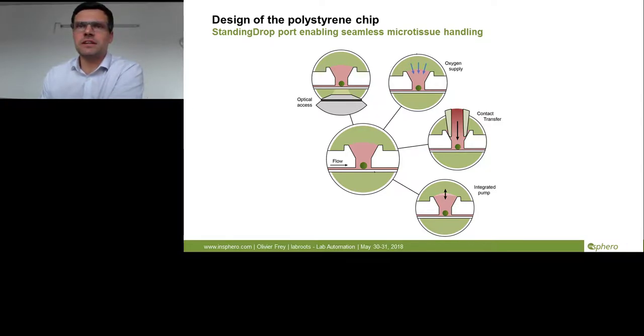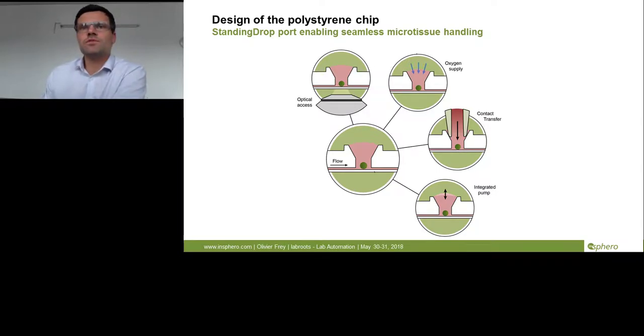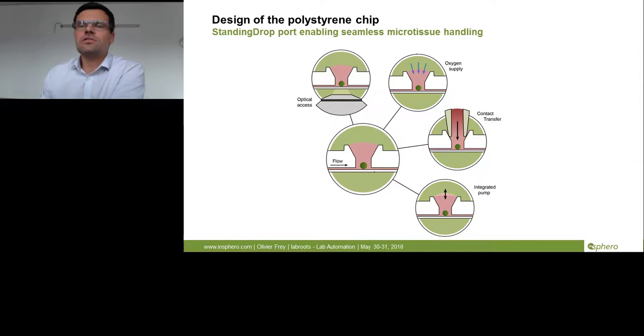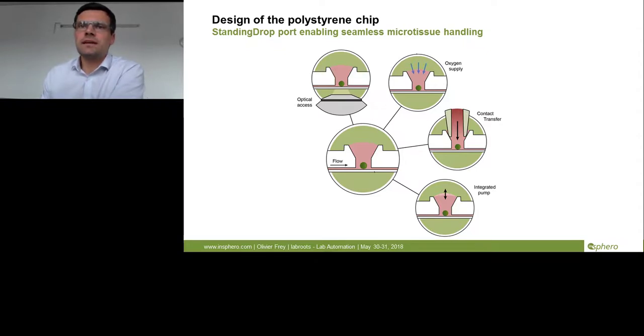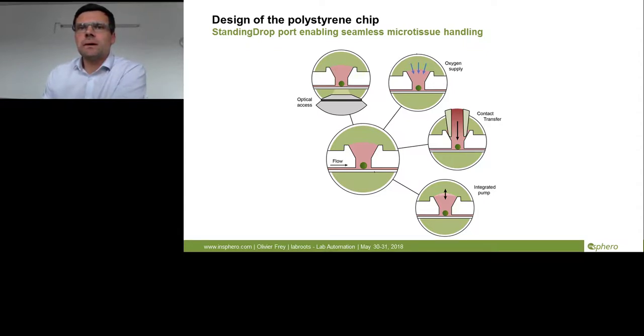We leave the standing drop port open over the duration of the whole experiment, providing minimal dead volume and several additional features: optical access from top and bottom for inverted microscopy, direct local oxygen supply through the liquid-air interface at the vicinity of the microtissue, and the ability to do a contact transfer — addressing the microtissue from the top for loading and removal. The liquid-air interface acts as a dynamic membrane enabling efficient medium exchange in that small dead volume.